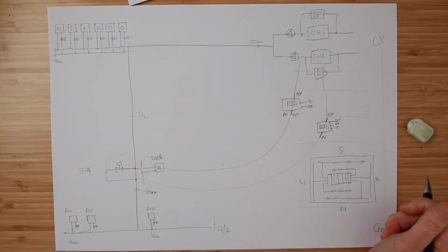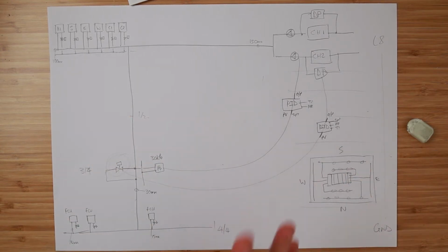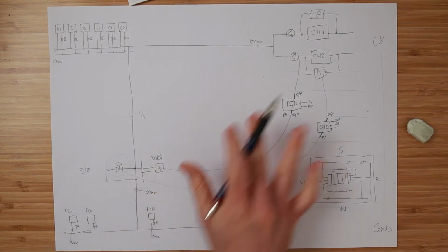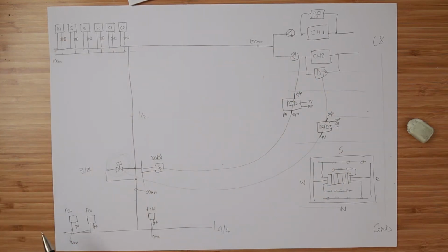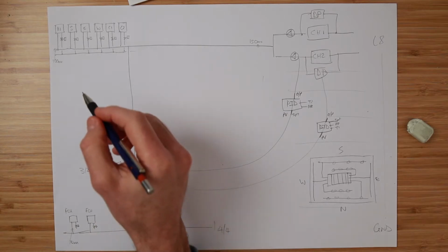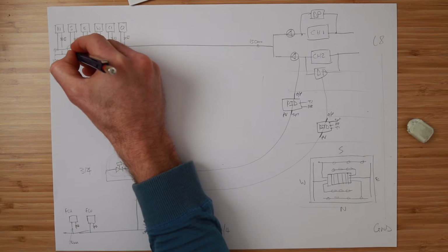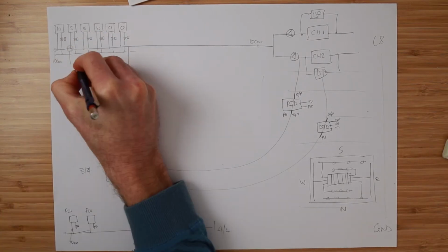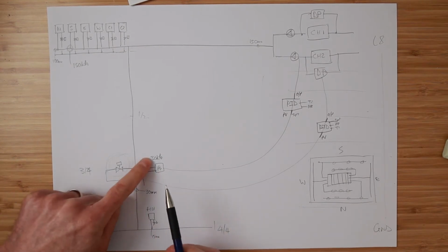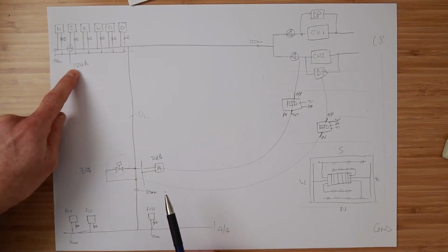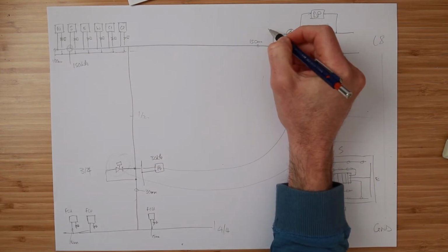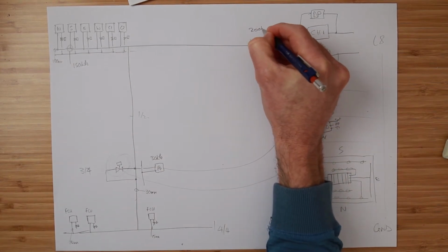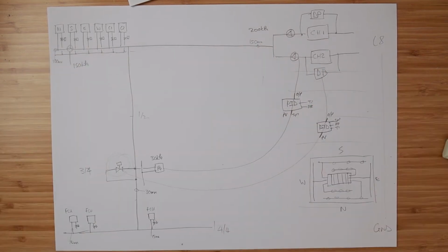So that's the system. Now, at this time that we're balanced, everything's sitting perfect, and we've got 30 kPa here, and the system's balanced. The pressure up here is obviously going to be much higher. So let's say that the pressure around about here, the pressure up there, 150 kPa. So at balance, our transmitter reads 30 kPa, it's 150 kPa there, and maybe the pumps are discharging at, maybe 200. So there we go. So here's the first problem.